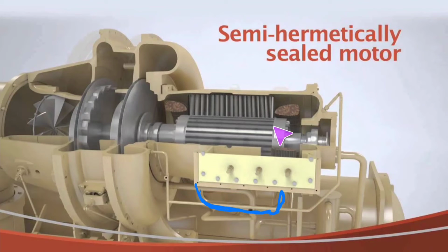And so that's something that we should talk about now. This is part of our refrigeration circuit on these machines, is we have to keep this motor cool. We keep it cool by pumping refrigerant into the motor housing. Back over here, you can't see it from this angle, but on this side of the system, there is a third pipe that lands in between these two drain pipes that is pumping refrigerant into the motor housing, and it goes through a little flash orifice plate that pushes liquid refrigerant in there and gives some cooling to the motor, and then the additional refrigerant as it cools the motor down just flows naturally through gravity back down into the condenser side of the system.